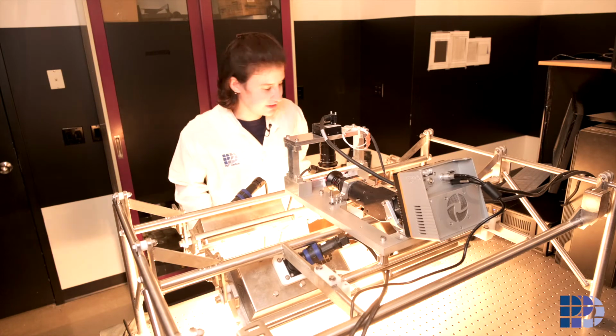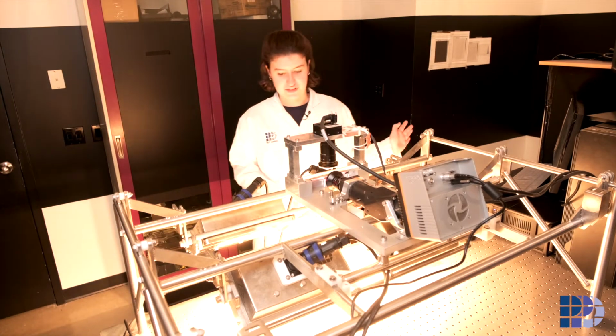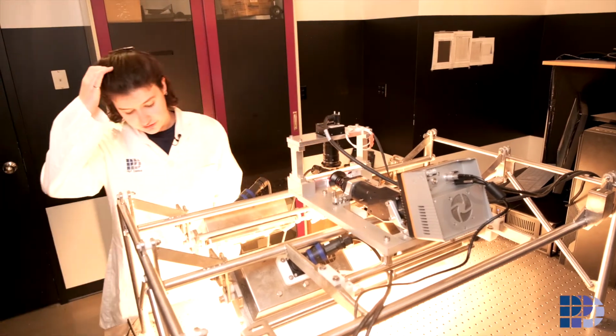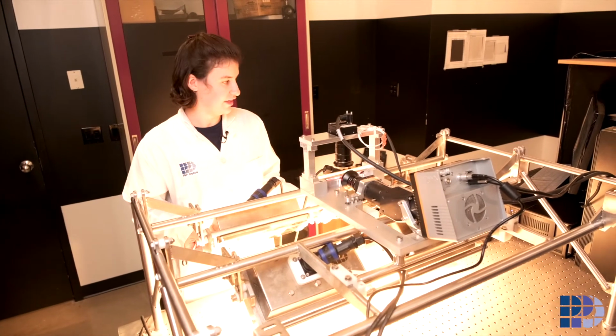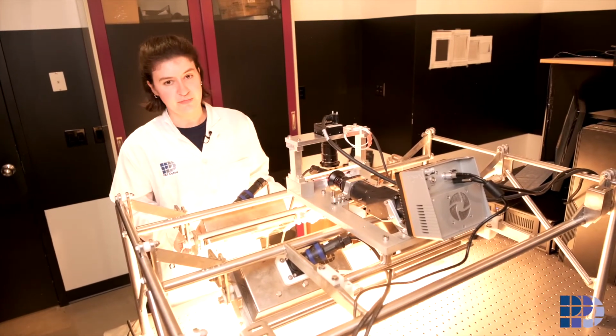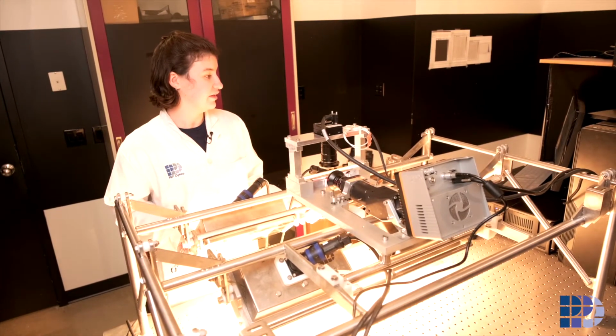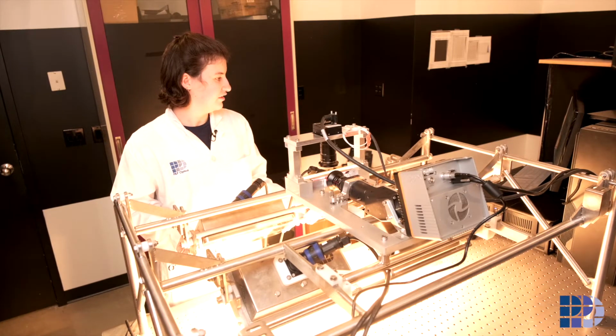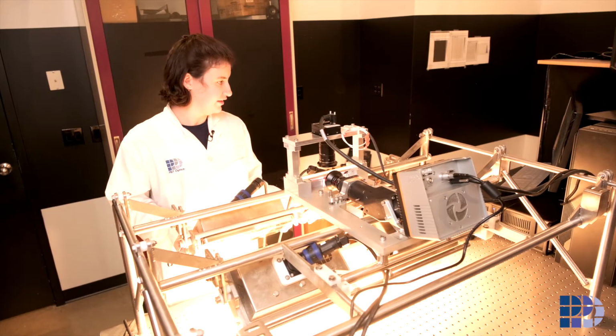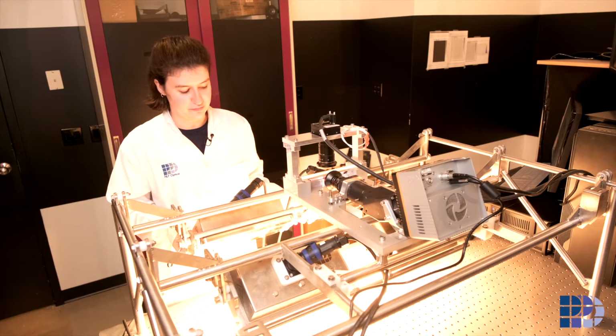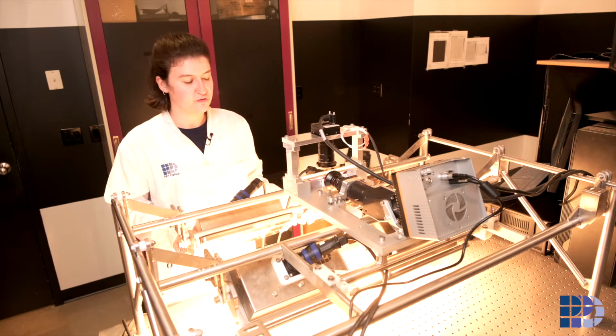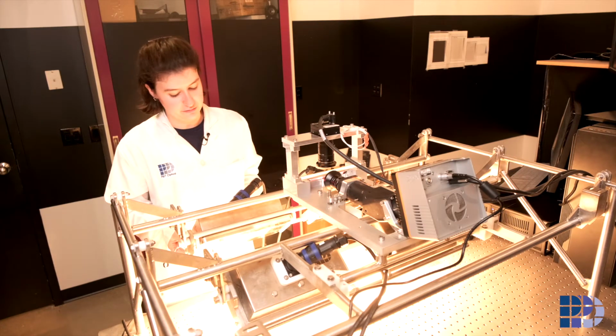So once I have the lights on and the live display set up, I would have the lamps loose so that I can adjust the angle, and I would be checking in with the live display such that at the height I'm working at, the calibration light profile is maximized, similar to what we were doing during the bulb alignment.